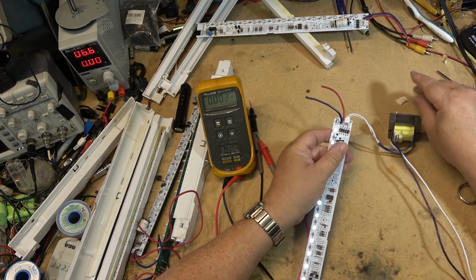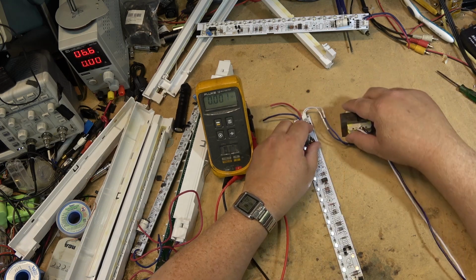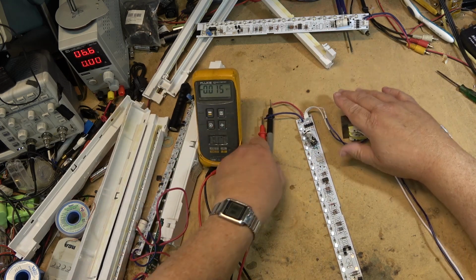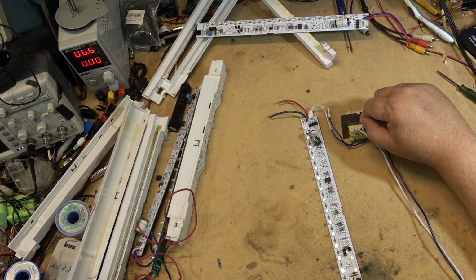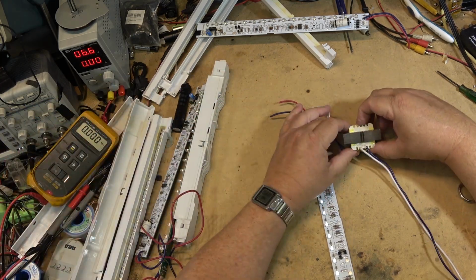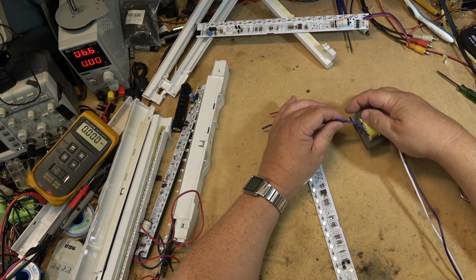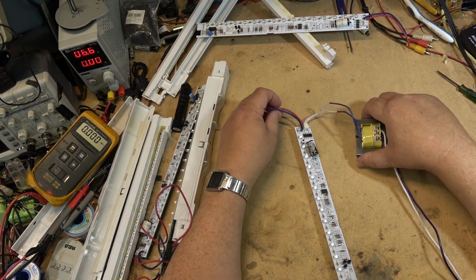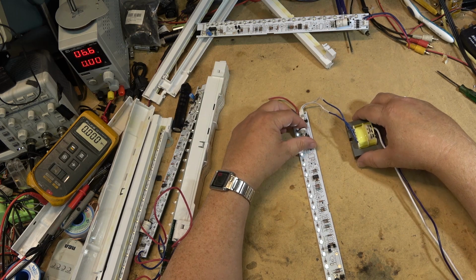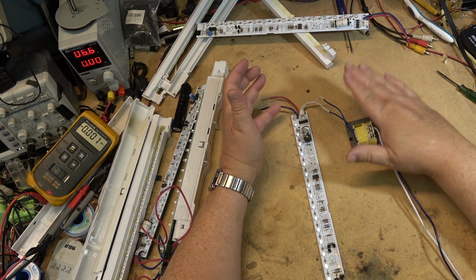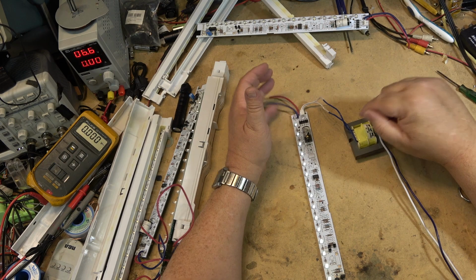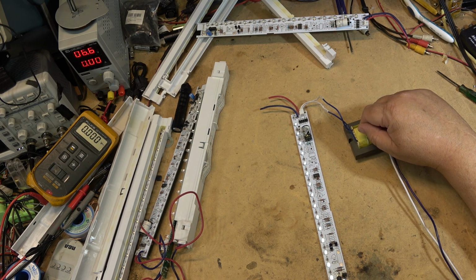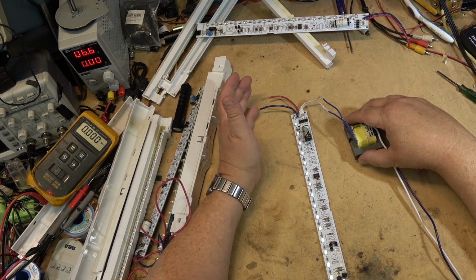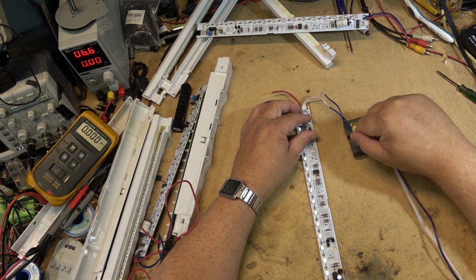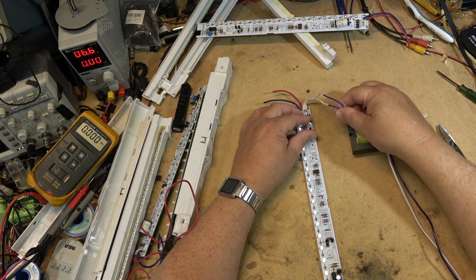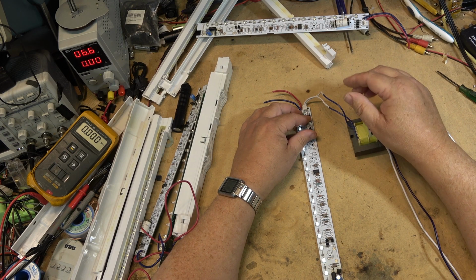The reason they've gone with a capacitor like that is, again, the input on the transformer - this transformer can handle up to 350 volts or 347 volts for those commercial buildings where they're using a 347 volt lighting circuit. So they don't have to run a separate lighting circuit for the exit signs. They can just run this transformer on the 347 volt or 240 or whatever their lighting circuit is, and put the transformer in directly. The output of this, of course, will be dependent on the input.